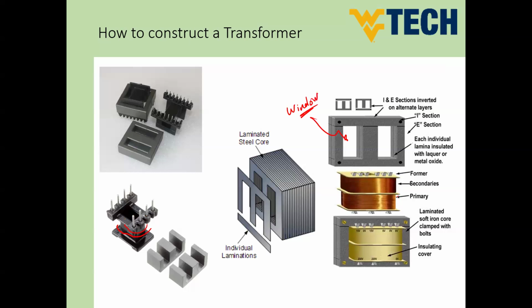The windings will be soldered on the terminals of these formers, as you can see here. These terminals can be used as the terminals of our transformer. And we have a similar shape here. This is called the former, and it's used to make the windings around it. After doing these windings, we can insert our core inside the gaps of this former. In the case of three-phase transformers, we would have a former here, another former here, and a third former here, and all formers will be inserted on the cores in order to make the three-phase transformer.